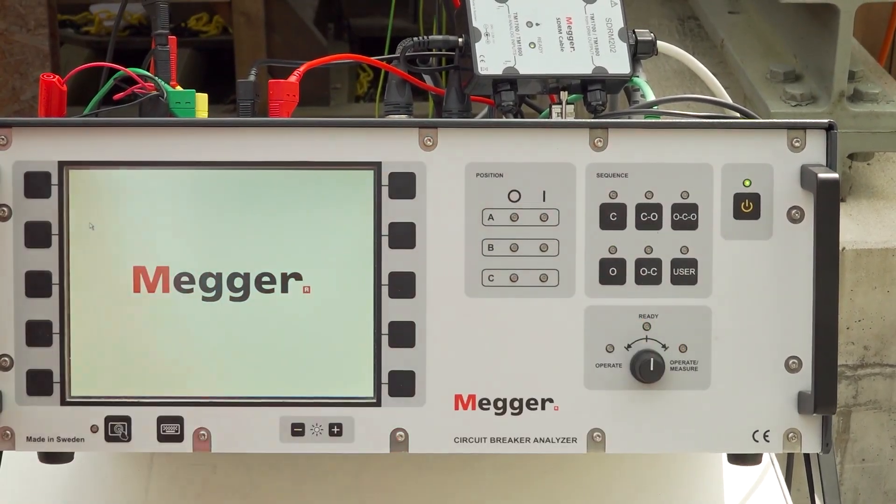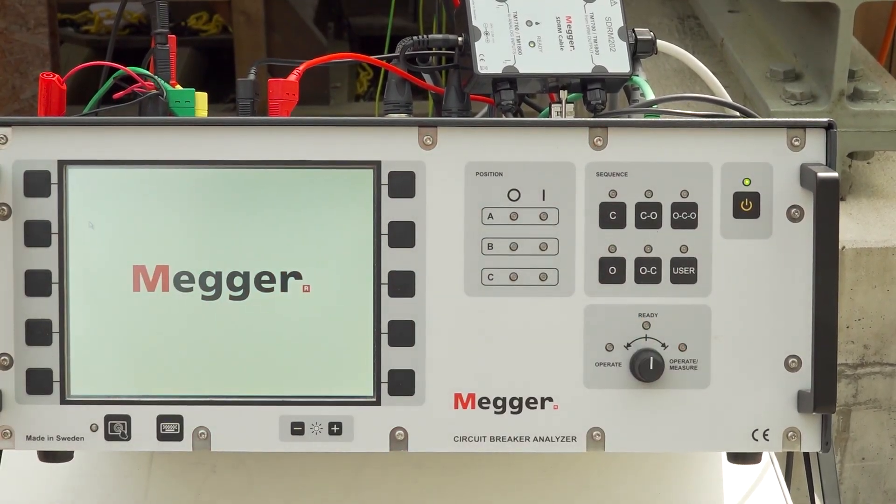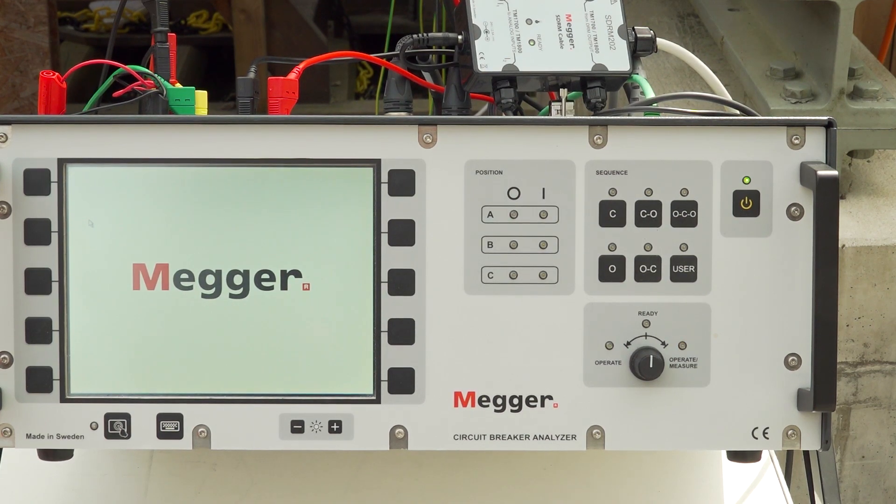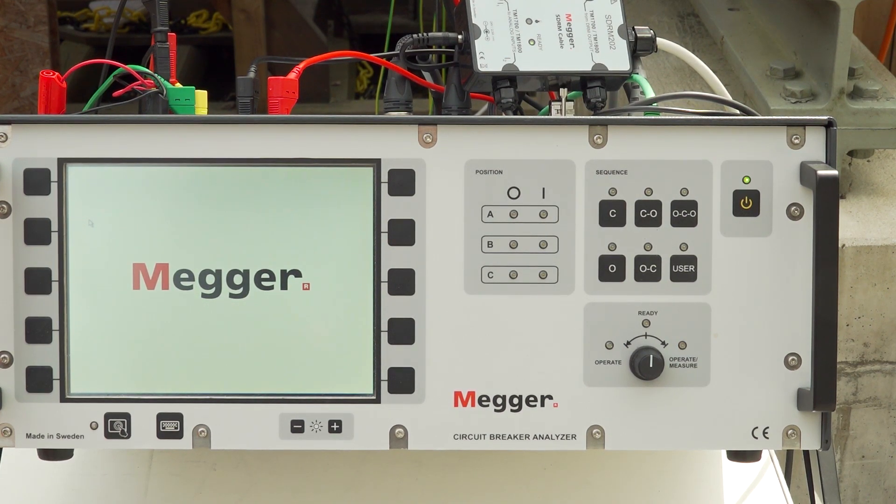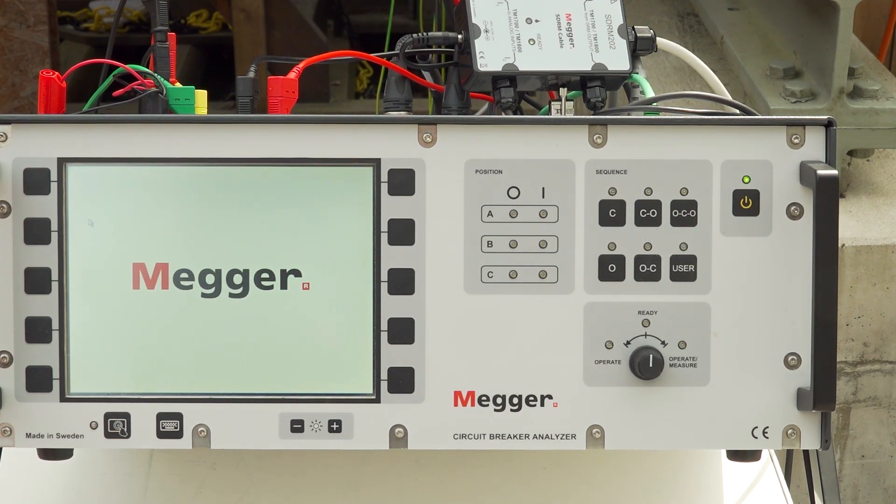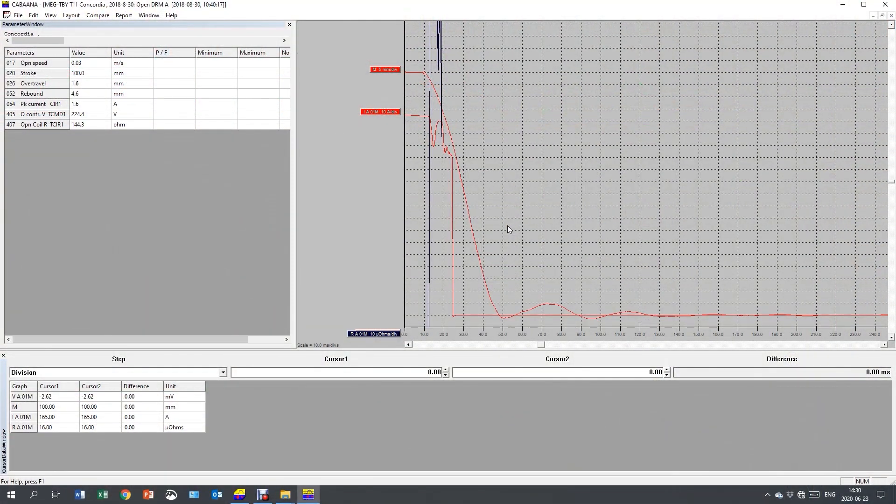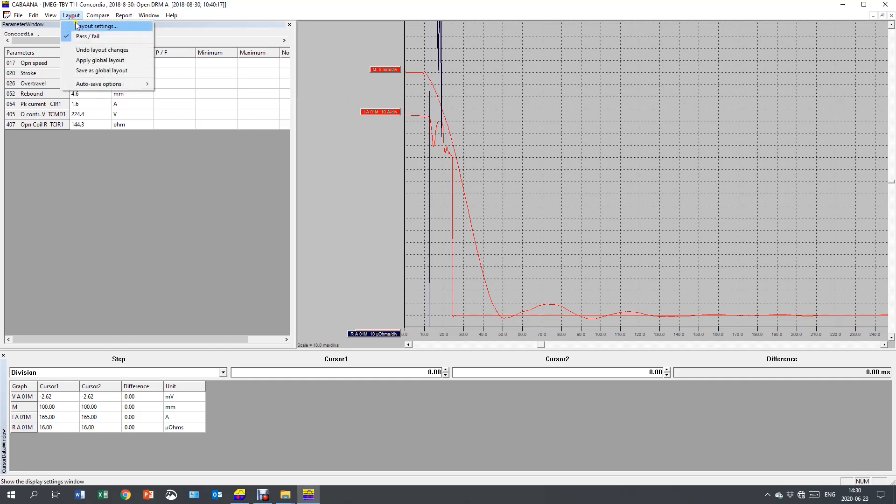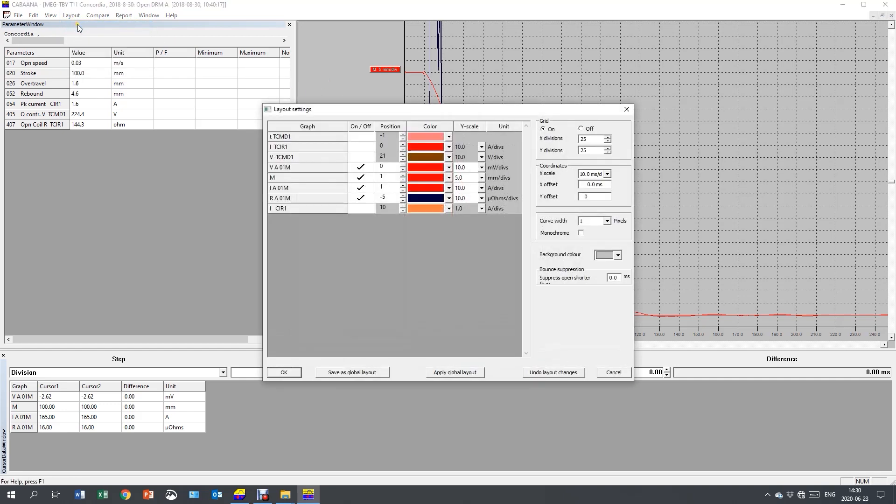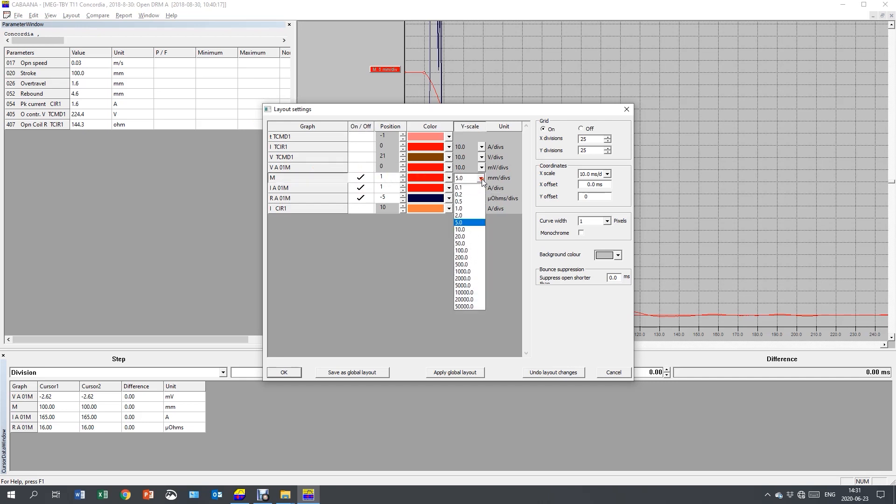I get the result on the PC screen. The first thing I have to do is change the graph's layout. I go to layout. And I change layout settings. I remove the voltage. I make sure motion, current and resistance is turned on. I change the Y scale. I want 20 for the motion. I want 100 for the current. And I want to change resistance to 200. I want the X scale to be 2 milliseconds per division.